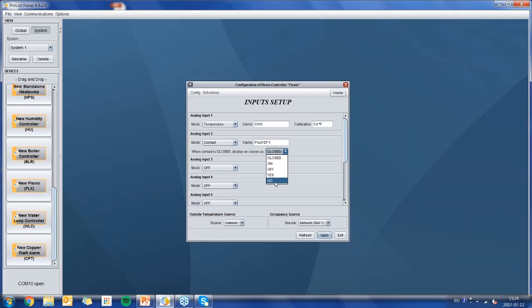Let's say I want to use Input 4, which is still relatively free, for pressure in inches of water. Maybe I want to control building pressure - there's a supply fan in the system maintaining a constant static pressure, but maybe there's some kind of relief fan or return fan that's going to modulate to maintain the building pressure.